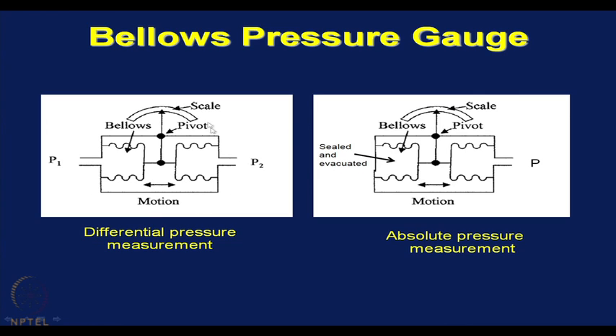Let us look at this arrangement. We have two bellows connected with each other, and we have attached a pointer to the link that connects these two bellows. Now, when these two bellows are connected to a differential pressure source, the movement of the pointer against this scale will be a result of the combined motion of these two bellows. So, in that case the movement of this pointer against the scale will be a measure of the difference between P1 and P2, or the differential pressure. If one of these pressures is atmospheric pressure, it is measuring gauge pressure.